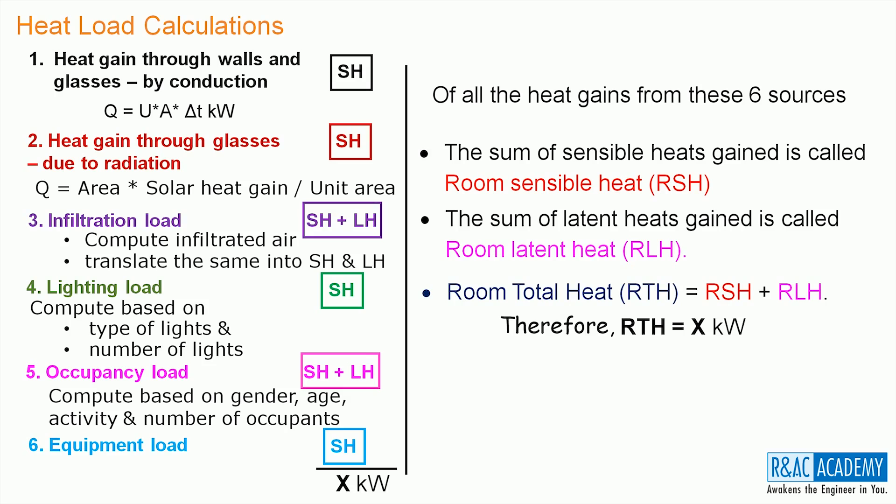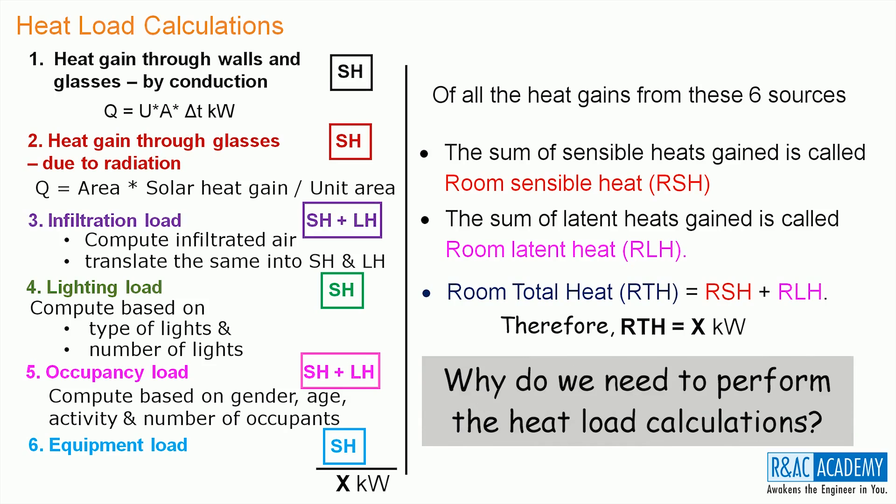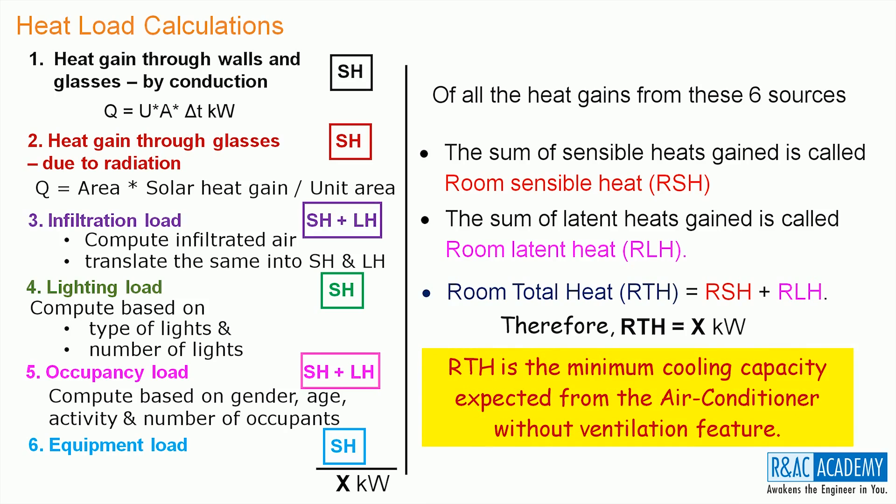Let us now pull the original question back. Why do we need to perform the heat load calculations? The heat load calculations gives us the value for x which is nothing but the RTH. And what is the significance of RTH? RTH is the minimum cooling capacity expected from the air conditioner without ventilation feature.